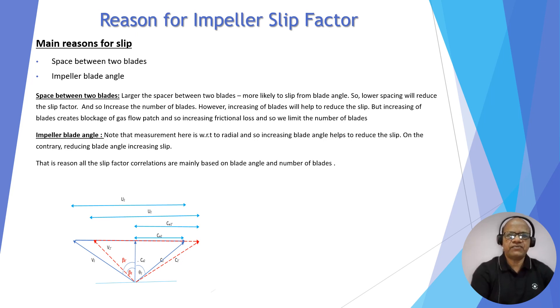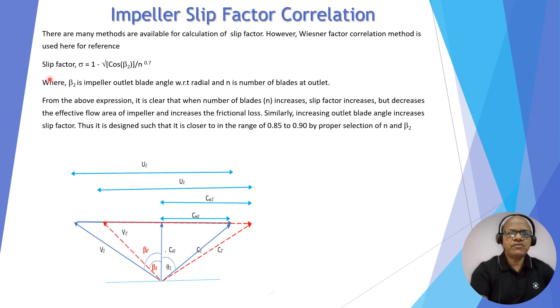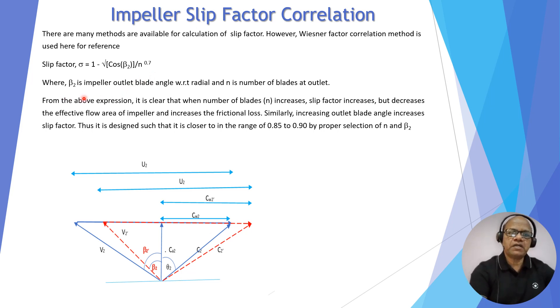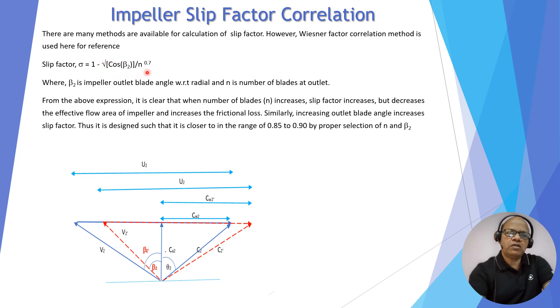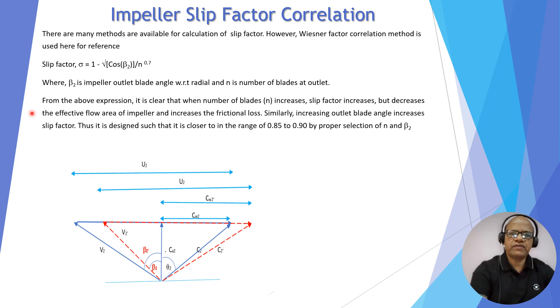All correlations for slip factor depend on two factors: β₂ and the number of blades n. There are many correlations available; here I have used the Wiesner formula, which is very useful: σ = 1 − (√cos β₂) / n^0.7, where β₂ is the impeller outlet blade angle measured from the radial direction, and n is the number of blades. If β₂ is very large, cos β₂ is smaller and σ is larger. Similarly, if n is very large, this factor becomes small and σ again becomes larger. So we must select appropriate values of n and β₂ such that the slip factor typically lies between 0.85 and 0.9.